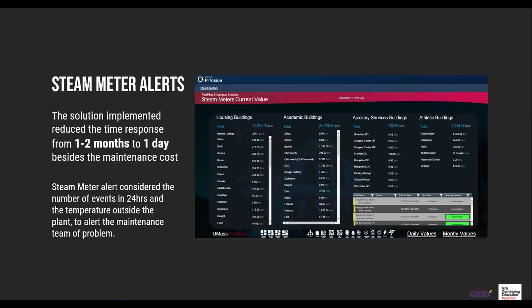The last dashboard I wanted to show today is the steam meter alert. This is interesting because we implemented it by combining analysis, event frames, and notifications. Now within 24 hours, if the steam meter is stale, we alert the maintenance team to verify the meter. Before this system was implemented, it took almost 2 months to verify that a meter was really stale. So we reduced the response time, but also reduced maintenance costs, because now the team can go directly to the meter that's having a problem.